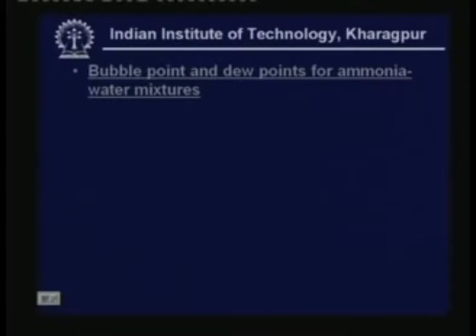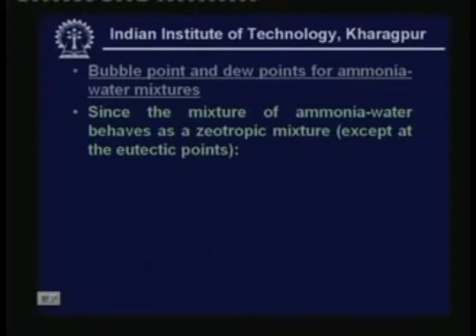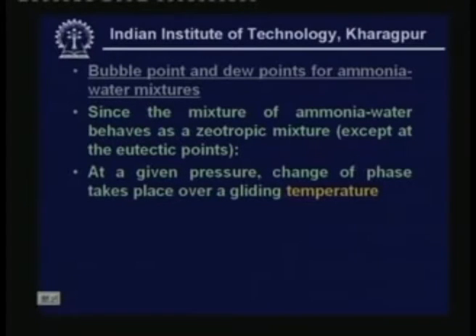Now let us introduce the important concept of bubble point and dew points for ammonia water mixers. This discussion holds good for any binary mixer which is a zeotropic mixer. Since ammonia water behaves as a zeotropic mixer (except at eutectic points where it behaves as an azeotropic mixer), at a given pressure, change of phase takes place over a gliding temperature — not at a constant temperature as it would for a pure fluid or azeotropic mixer. This is the nature of zeotropic mixers.